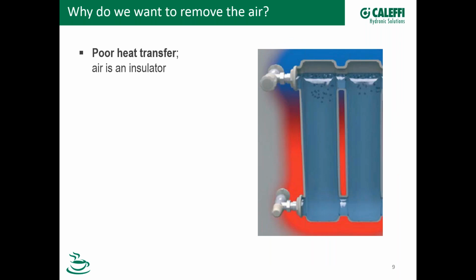So why do we want to remove this air? Well, I think one of the more important reasons is heat transfer. Air is a really good insulator. In fact, it impedes the conveyance of heat. For example, a given volume of water can absorb about 3,500 times more heat than the same volume of air. And you can see this thermal diagram here indicates how that air pocket up there is going to be much cooler than down below where you just have water.